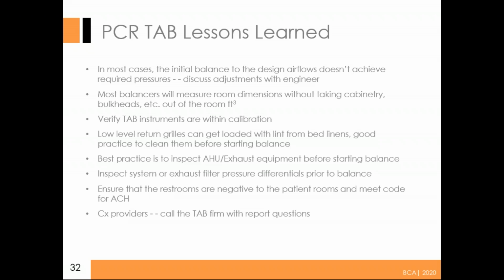Most balancers will measure room dimensions without taking cabinetry, bulkheads, and so forth. What we've always looked at, especially when you have to meet air changes per hour, we try and use the raw dimensions of the room before we start taking out bulkheads, cabinetry, and everything else. We always figured if you can make it with a raw room, you're actually giving a little extra air changes per hour for that room. Like always, verify that your TAB equipment is in calibration. Hopefully we do that before we get on site, knowing that our equipment is in calibration.